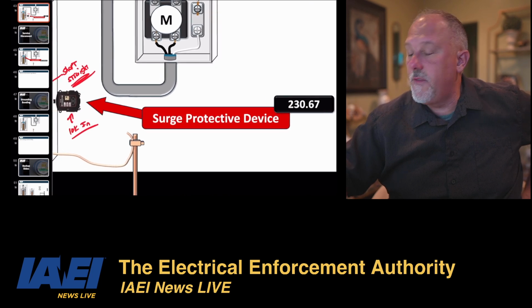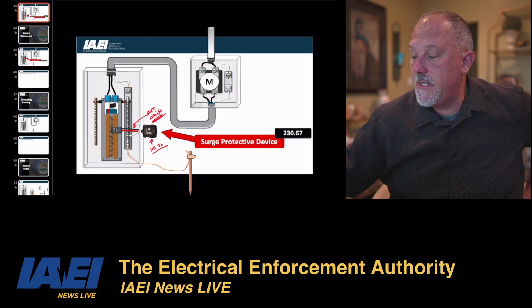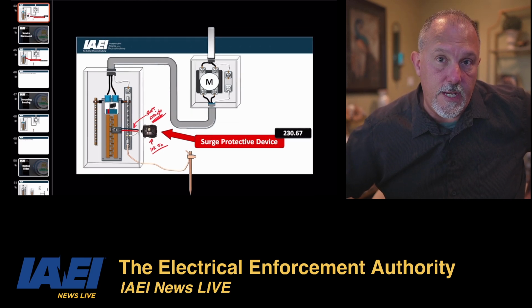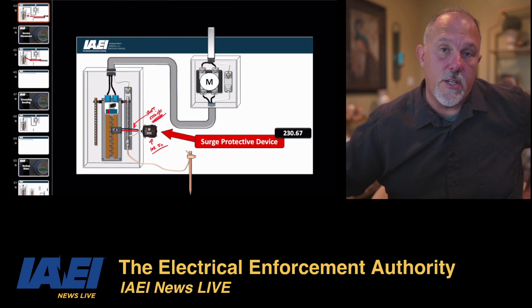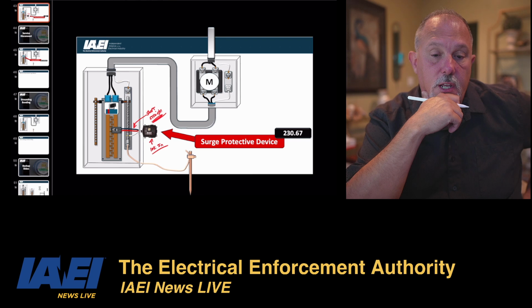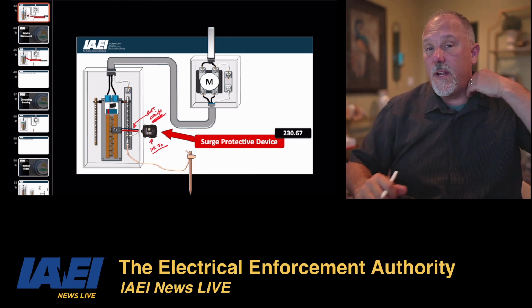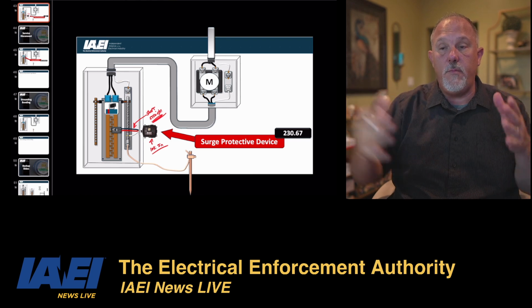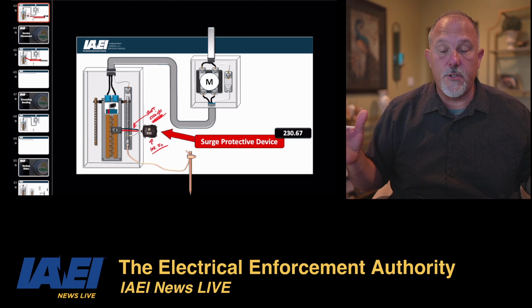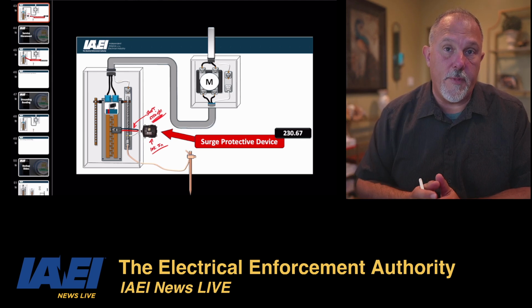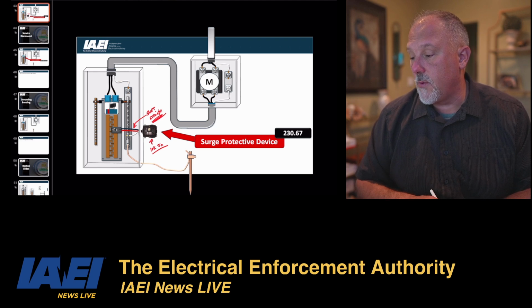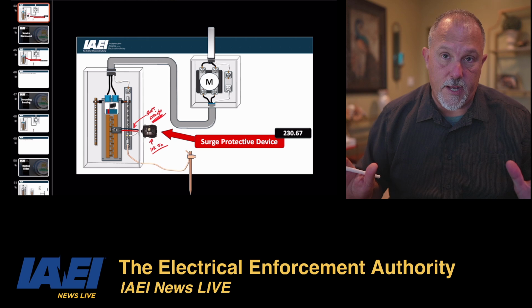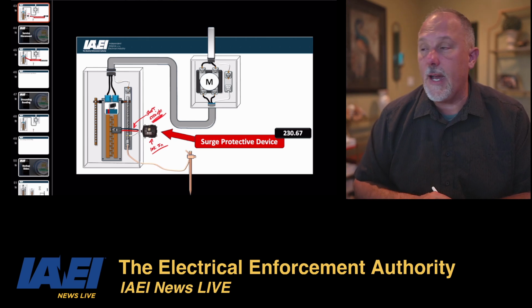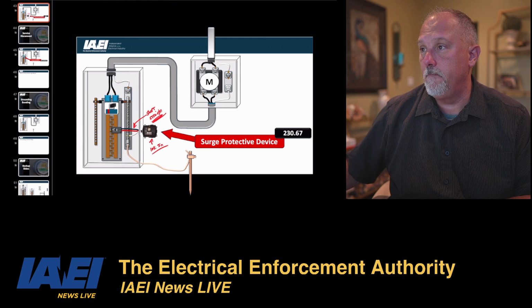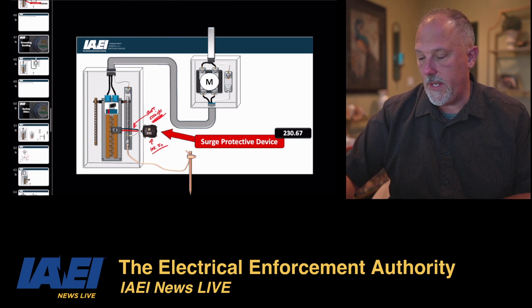So that is 230.67. And don't forget, please take a look at Articles 215 and 225 as well, because there are surge requirements over there on feeders as well. So you may run into a case where you have service equipment, and then you come down to your meter centers as feeder equipment, not service equipment, and those are going to have surge requirements as well. Please make sure you're buying and specifying the right products to meet the 10kA In requirement as well. And that's your 230.67.